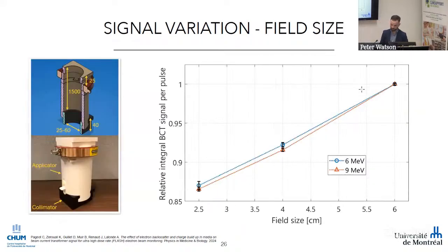That's true for the SSD. It's also true for the field size. In this case, we place our BCT in a 3D printed applicator in which we can put collimators to change the field size. And depending on the size of this collimator, we get a different reading. When we have a smaller field size, we have a lower BCT signal, which would work with the backscatter hypothesis.